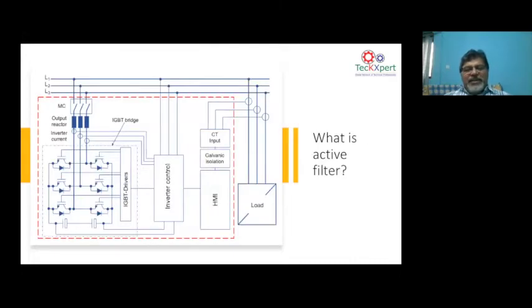So now you can see here, you have a load at the right side. You have a CT input coming to the active filter. The active filter has IGBT switching technology, and it is switched in and switched out at a particular frequency, depending on the frequency to be compensated in the network. If you want to select all the frequencies from the second harmonic to the 50th harmonic, you select the filter as a broadband filter. The switching will take place and remove the harmonics between the second and the 50th.